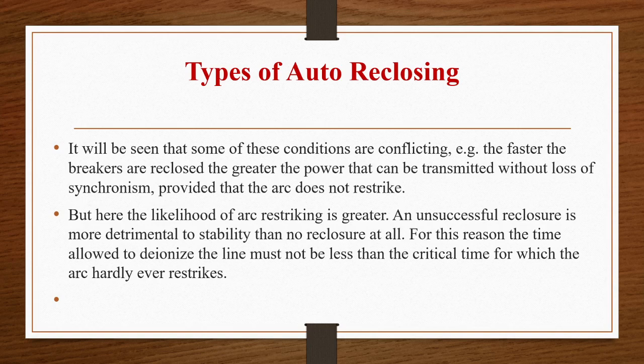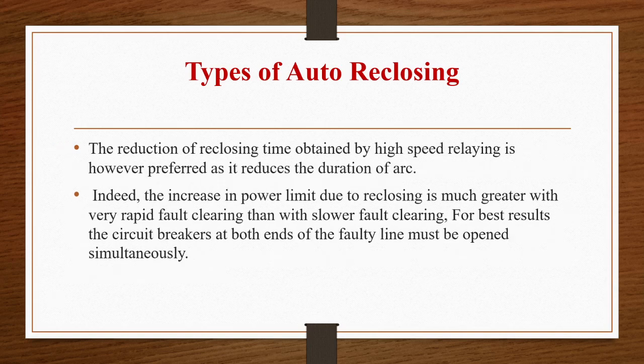So what we have seen here is that the faster the circuit breakers are reclosed, the greater is the power that can be transmitted without loss of synchronism. But here the likelihood of arc restriking is greater, and unsuccessful reclosure is more detrimental to stability than no reclosure at all. For this reason, the time allowed to deionize the line must not be less than the critical time for which the arc hardly ever restrikes. Extinction of arc and all this we have seen in the subject switchgear and protection. Students, you can watch those videos of switchgear and protection for arc extinction and explanation in detail. The reduction of reclosing time obtained by high speed relaying is however preferred as it reduces the duration of arc.